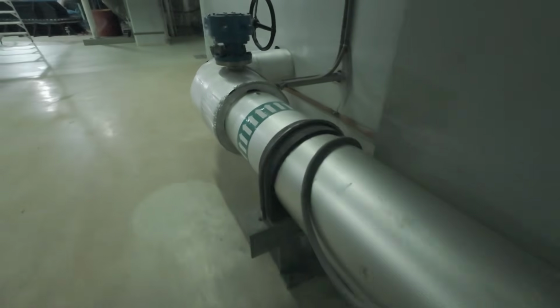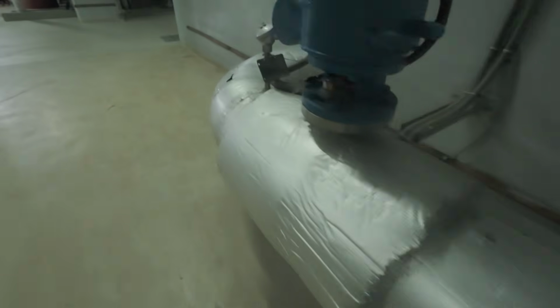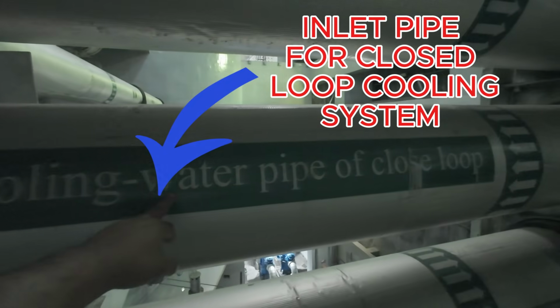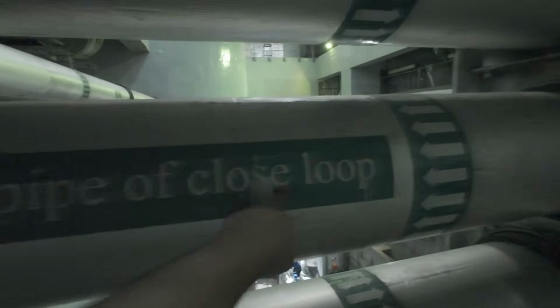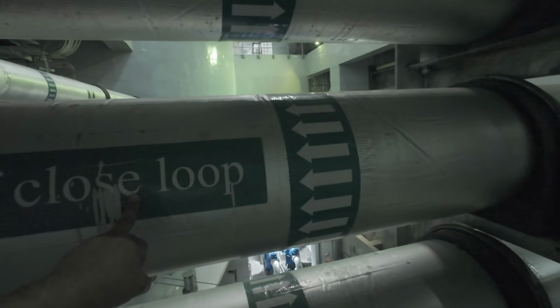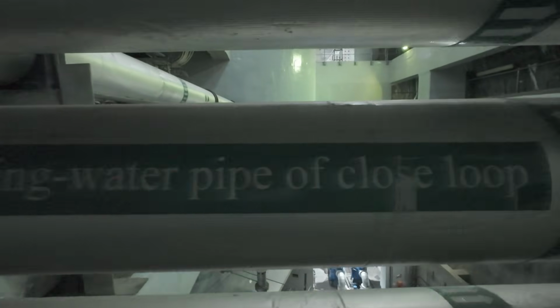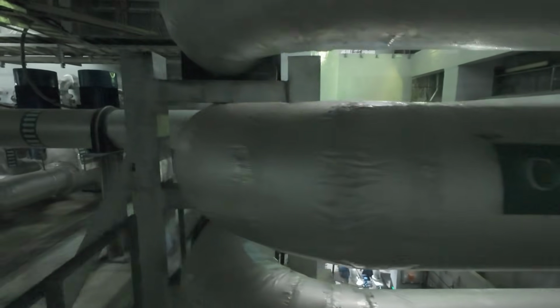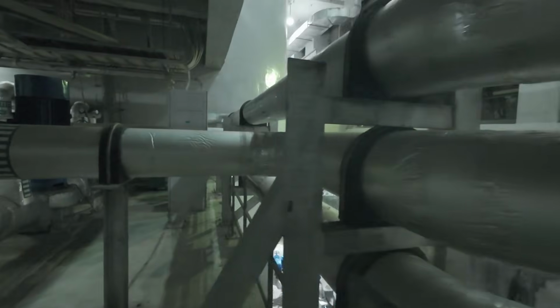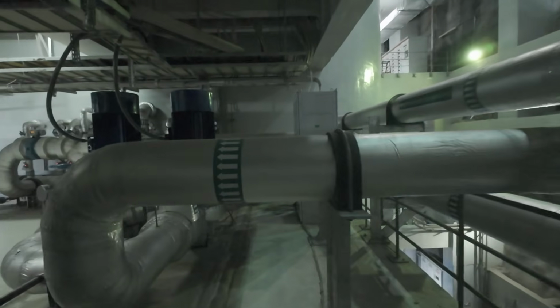Then comes the upper guide bearing. Its job is to stabilize the upper rotating shaft. Then the lower guide bearing, and finally the turbine guide bearing near the turbine side. Each one produces heat continuously. The cooling water absorbs heat from all the systems and returns hot to the heat exchanger, where the entire cycle starts again over and over, 24 hours a day, sometimes for decades.